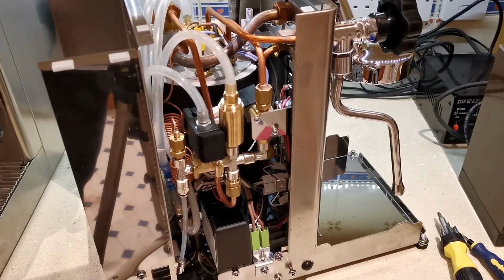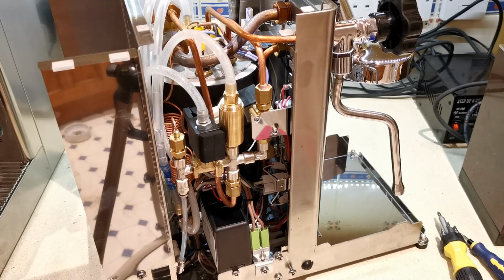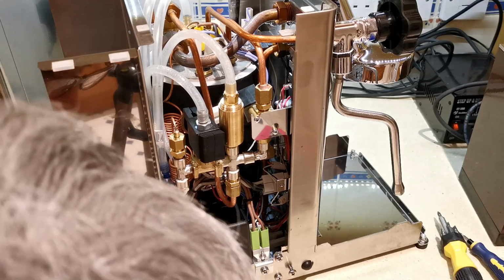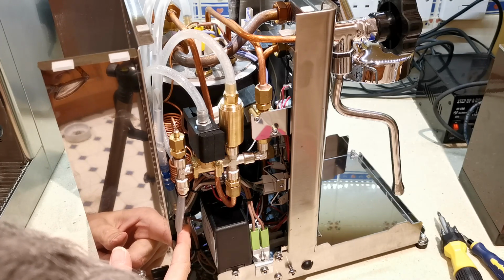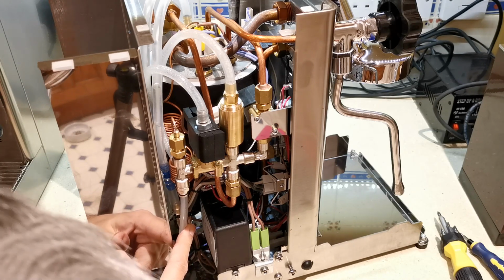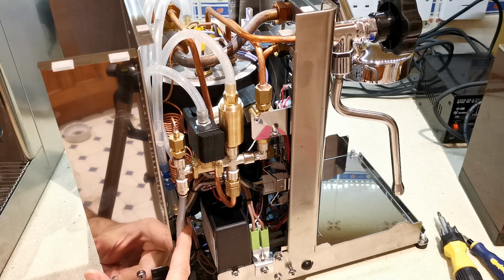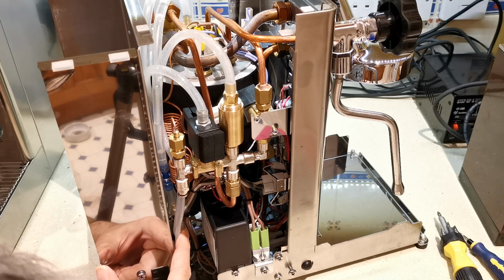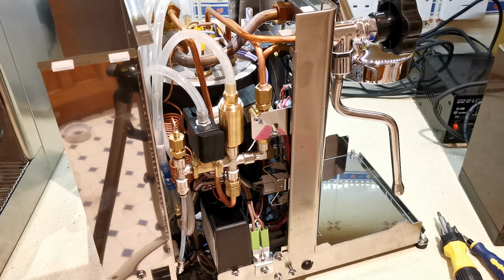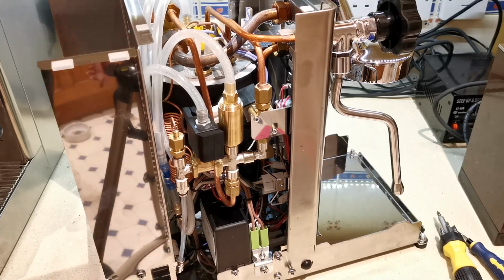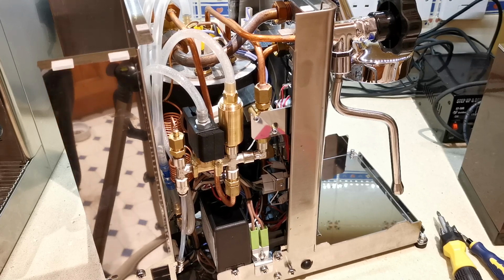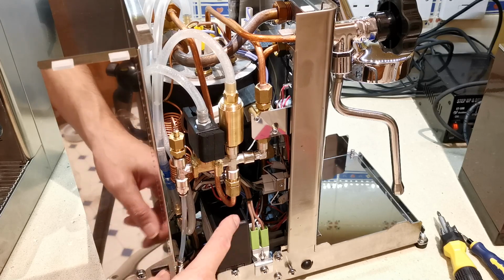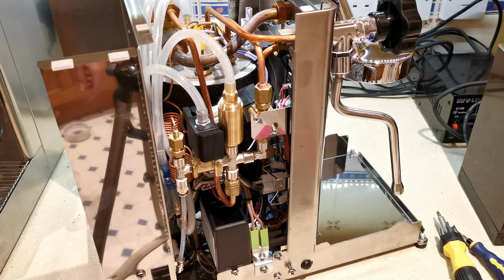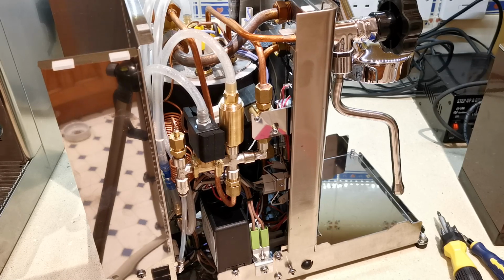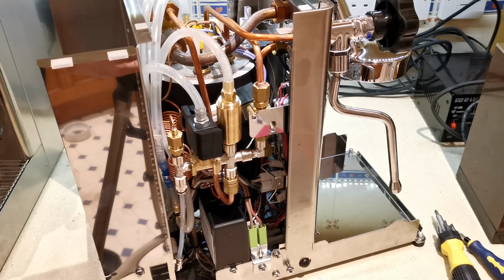And here we come to the business end of the machine. Here is your Gicar box. It's an SW18. Oh, well, it's their own. You're going to need to get it from Lelit because they'll have their own firmware on it. They've got the various temperatures coded in. These boxes can actually be programmed with custom firmware. A lot of companies do that now, so you can't just use standard Gicar boxes, and Lelit will have their own custom firmware for this box. So if ever you get a problem with it, you'll need to get a Lelit one.